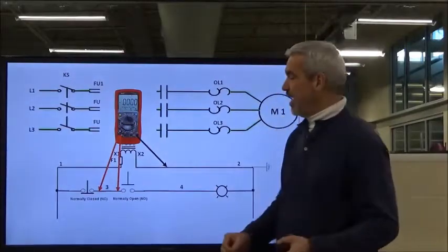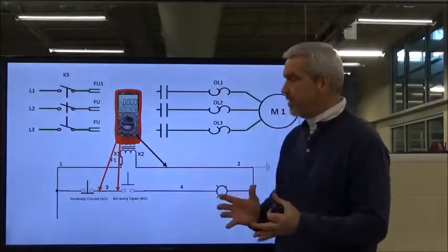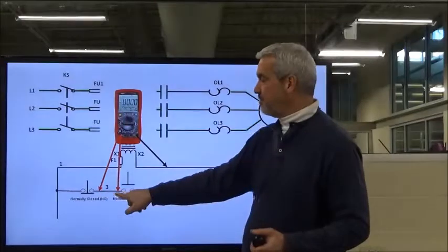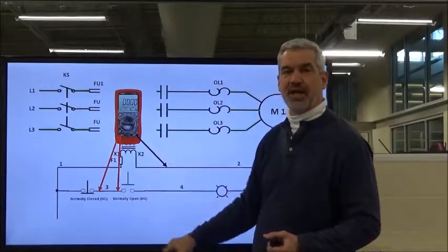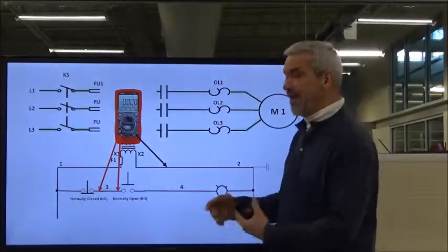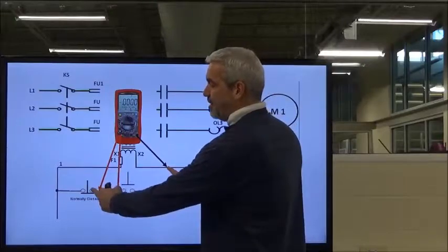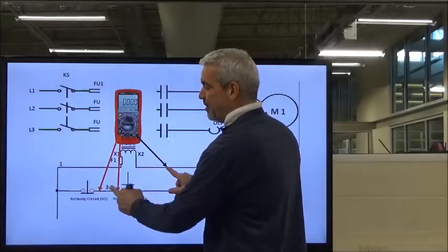And then as I come over here, I find my normally open switch wherever it's at on the machine. I open the panel or the back of the switch, and I should see wire number 3 going to the normally open set of contacts on that push button switch. That's the one I want to check, because we know it came from here. I want to make sure it made it from here to there.